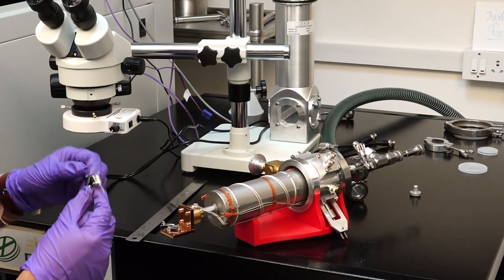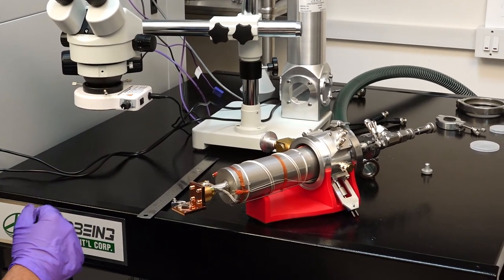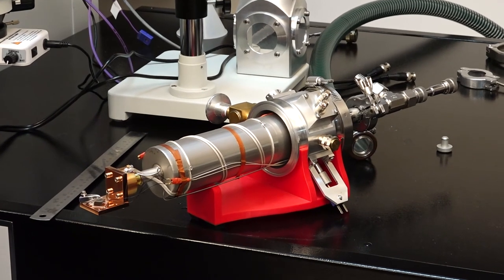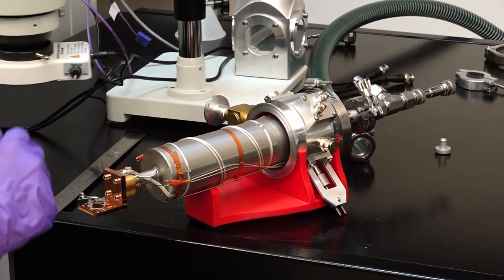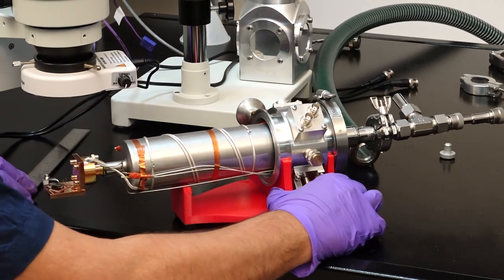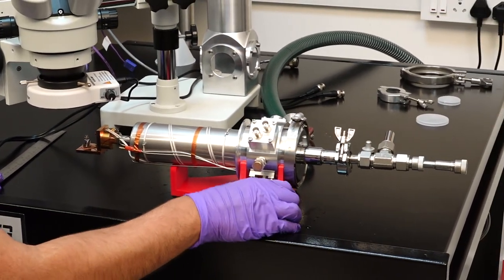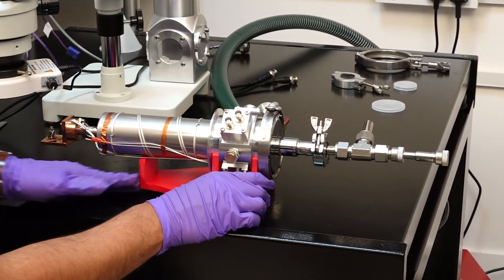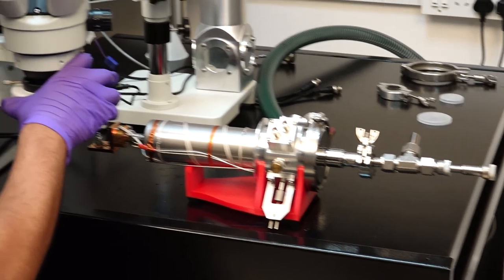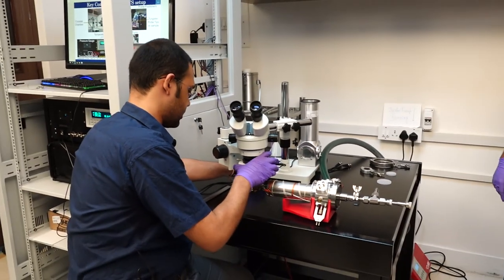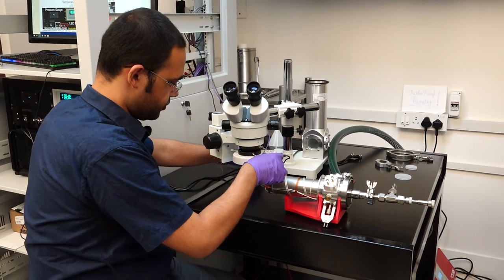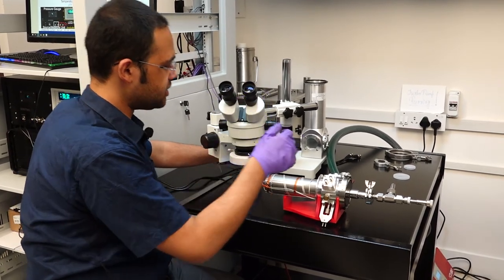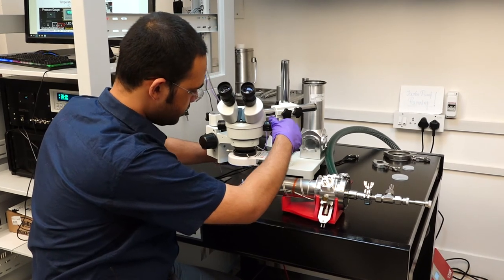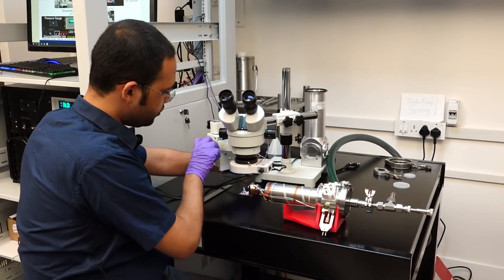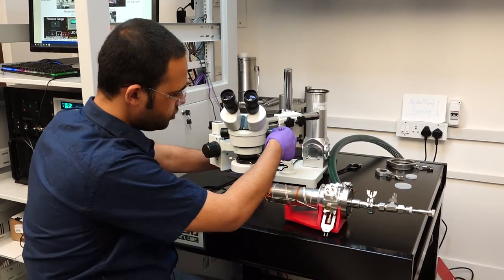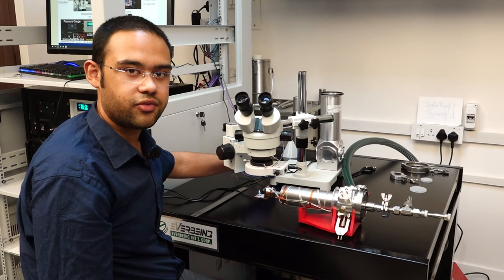Once we find the tips, we can slowly land these tungsten tips using these controls. One more important aspect while we are probing smaller pads which are not visible to the naked eye is to use these microscopes. So what we generally do is we put the stage, we turn on the microscope light and using the eyepiece, and by focusing, we can do the focusing movements, we can change the magnification, and then we can land our probe tips for on wafer measurements.